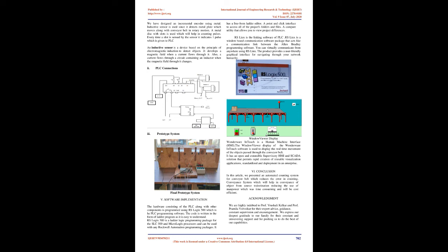For implementation, by designing an encoder, we have designed an incremental encoder using metal. An inductive sensor is used since it detects the metal plate which moves along with the conveyor belt in rotary motion. A metal disc with slots is used, which will help in counting pulses. Every time a slot is sensed by the sensor, it indicates 1 pulse, which is given to the PLC.